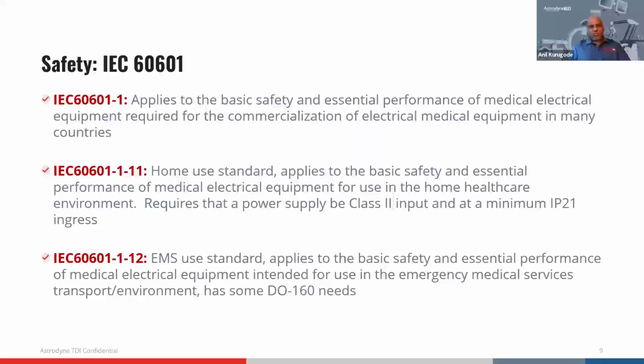In the industrial world, the safety and EMI standards are all different. The safety standard mandates certain requirements, whereas emissions and immunity are left to the system designer to determine what's acceptable. There's no regulatory body there - yes, there are procedures on how to evaluate them and define acceptance criteria, but in the medical world it's explicit. The standard tells you clearly for what class of equipment, what level of performance is acceptable.